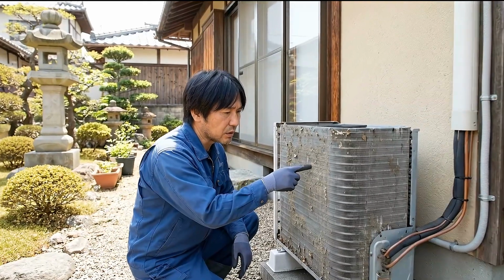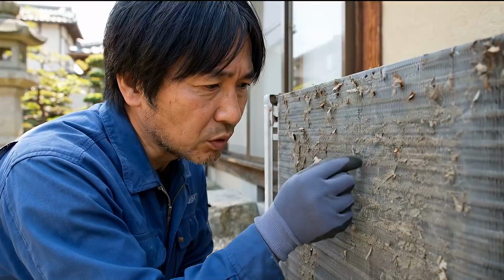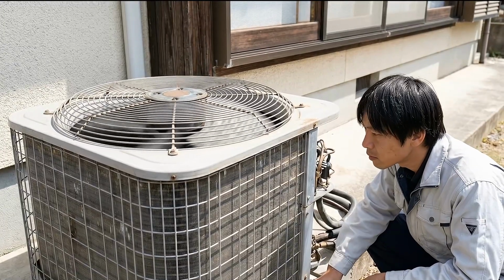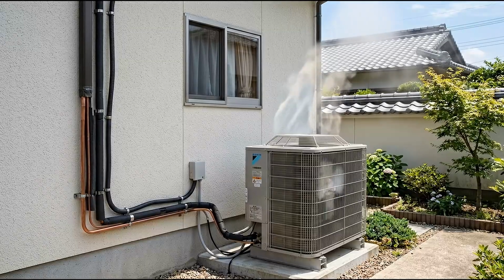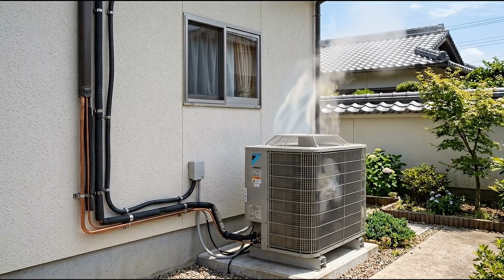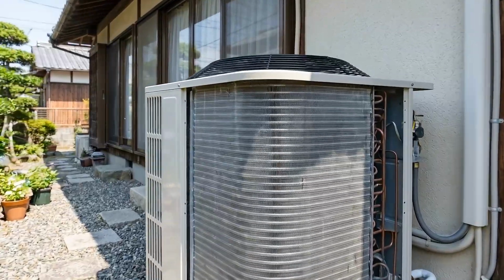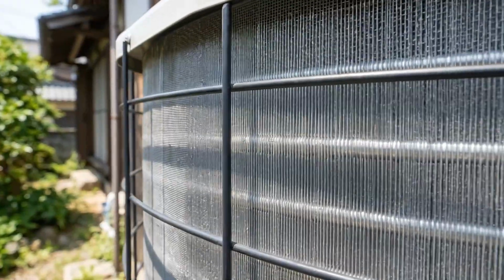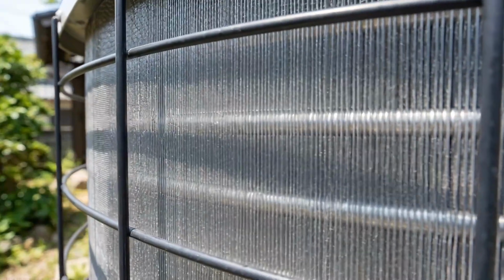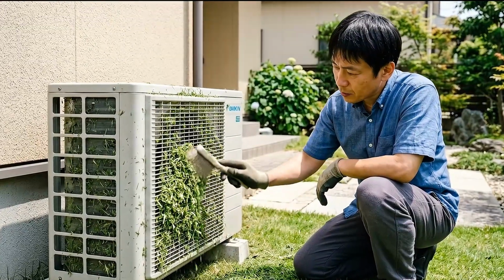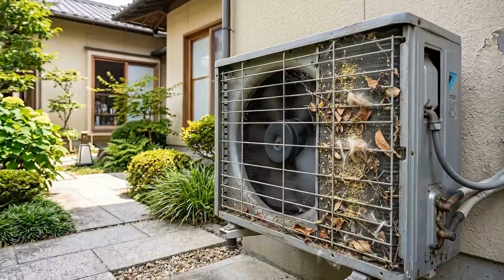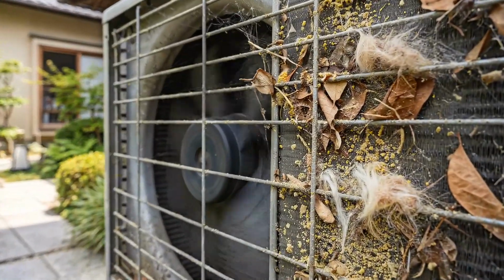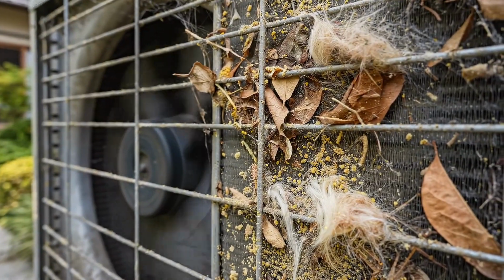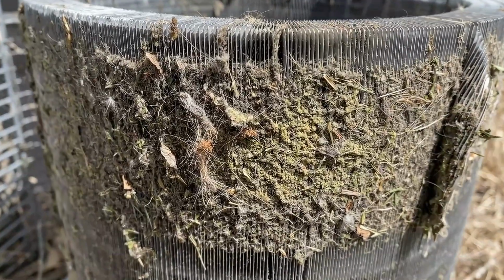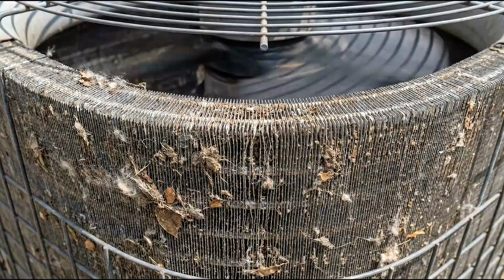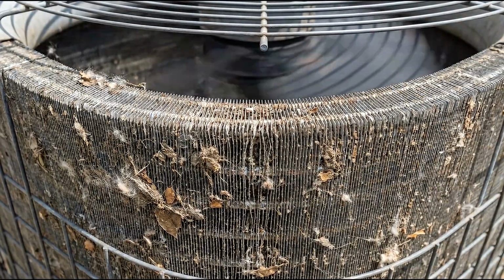Once you are past the filter, the next part most homeowners ignore is the condenser coil, the big metal box sitting outside your house with a fan on top. That outdoor unit is the release valve for all the heat your system pulls from inside. The condenser coil wraps around the inside of that housing, and its thin aluminum fins are designed to let air pass through freely so the heat can dissipate. But those fins are exposed to everything. Grass clippings from the mower, cottonwood fluff in May and June, pollen, dust, spiderwebs, leaves, pet hair drifting across the yard. Over a season, that buildup forms an insulating blanket on the coil surface that blocks airflow exactly the way a clogged air filter does inside the house.